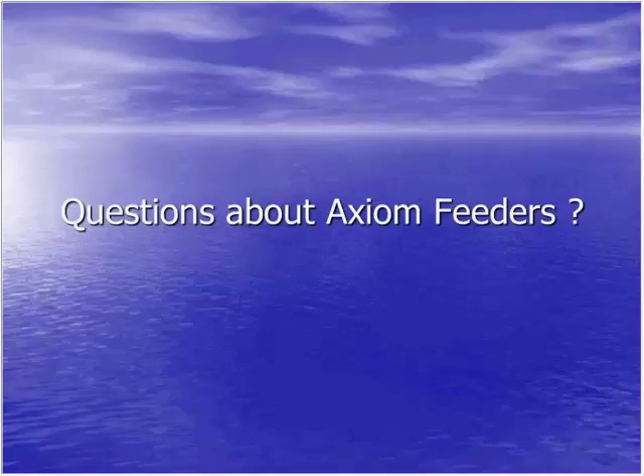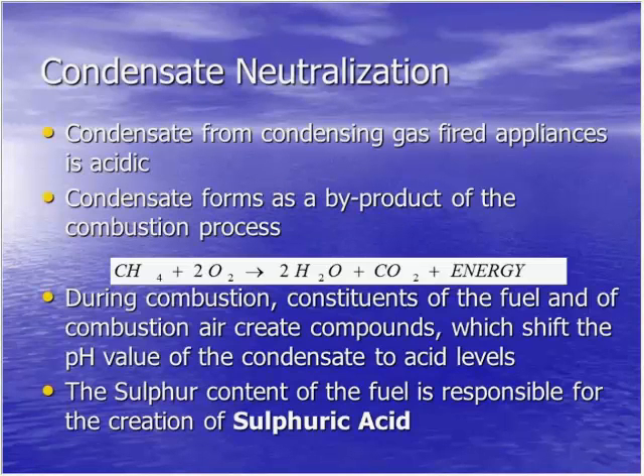So moving along here to condensate neutralization. This is a topic that's been talked about for quite some time, ever since we started using condensing boilers here in North America. The condensate from these condensing gas-fired appliances, be it a boiler, a hot water heater, furnace, it's acidic and it can corrode drains. So this condensate forms as a byproduct of the combustion process. We've got the little equation there with natural gas with oxygen create H2O, CO2, and obviously energy, which is what you want out of it.